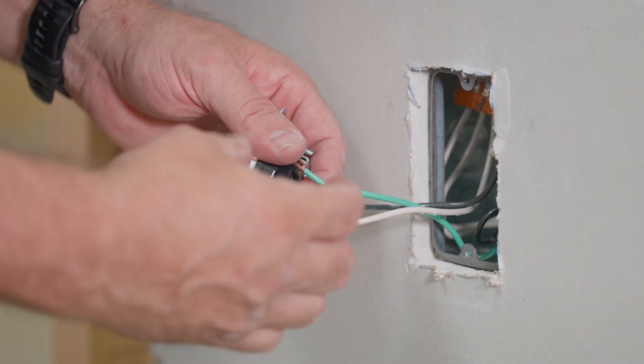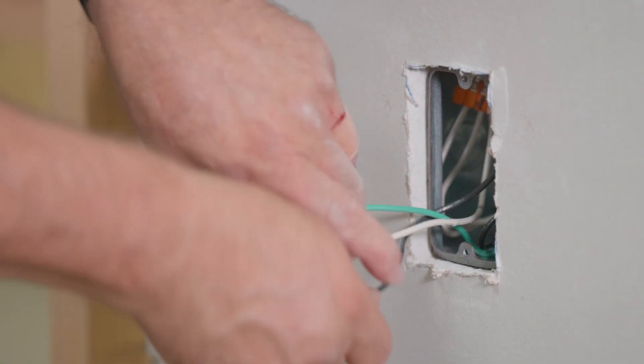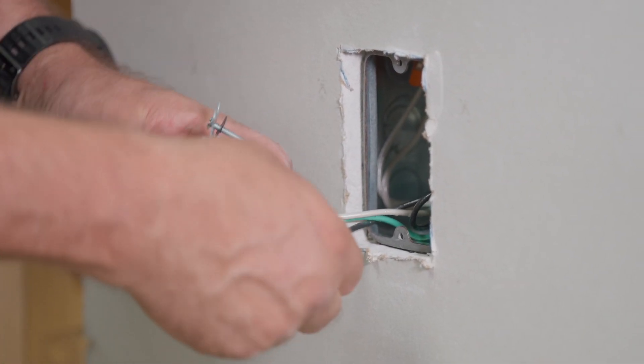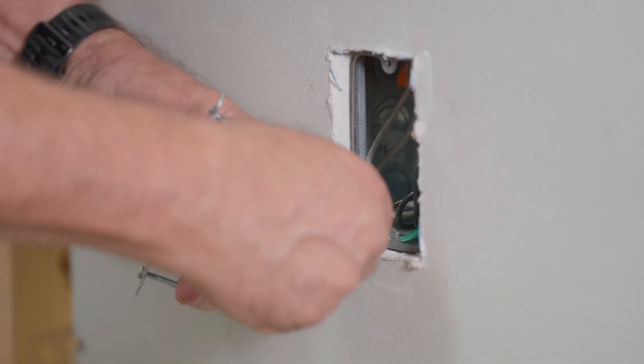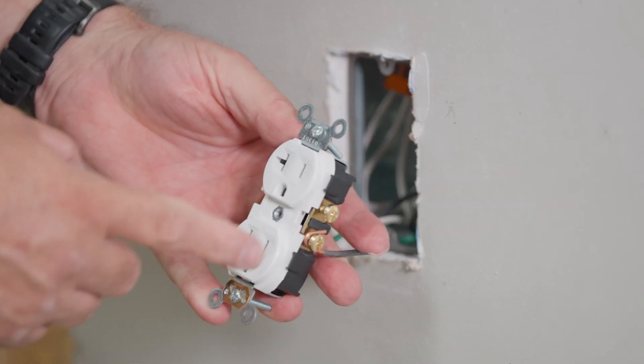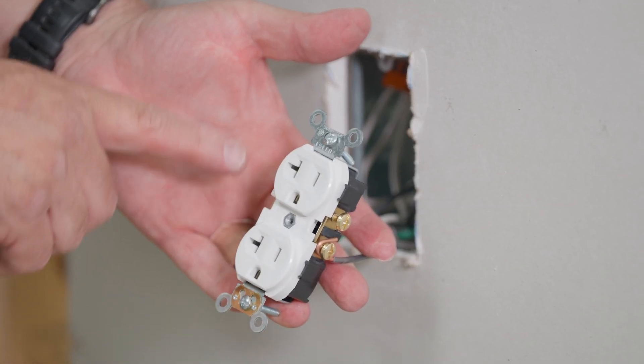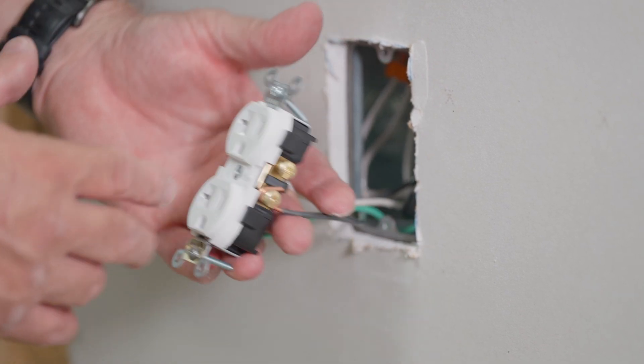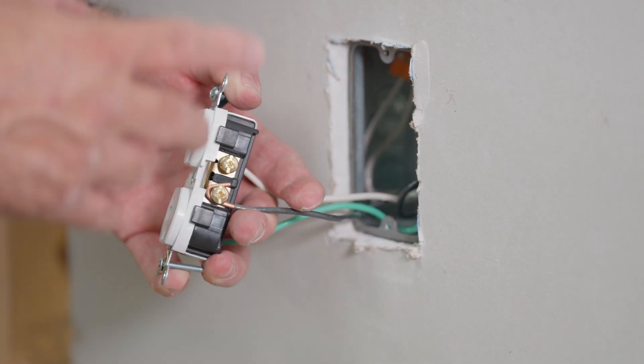Now what we'll do is turn this thing over to right side up. There you have it. And then we'll take this again, put it on the terminal on this side. You'll notice these are brass colored and these are silver colored. The silver colored terminals are for the neutral or grounded conductor. The brass is for the hot conductor.